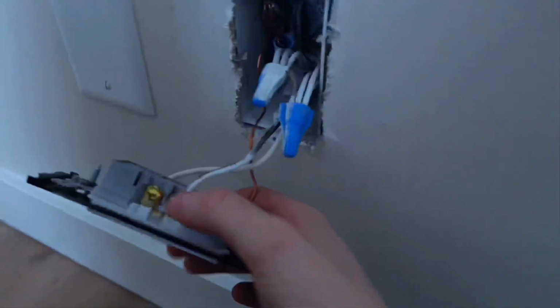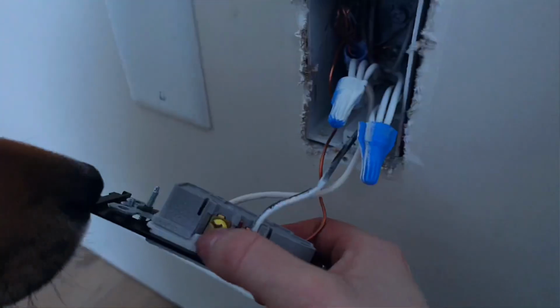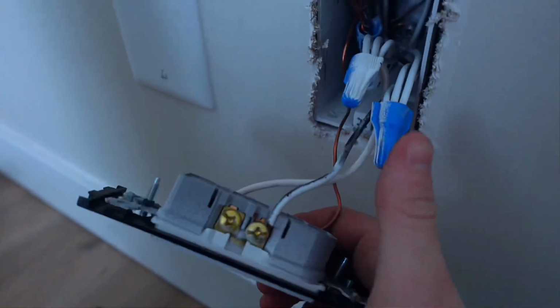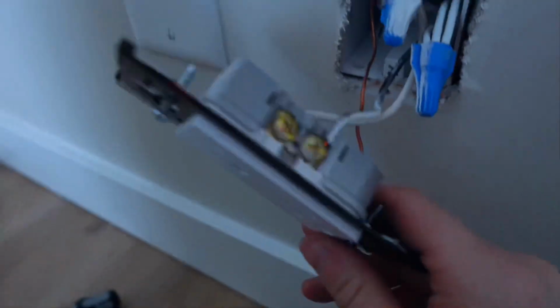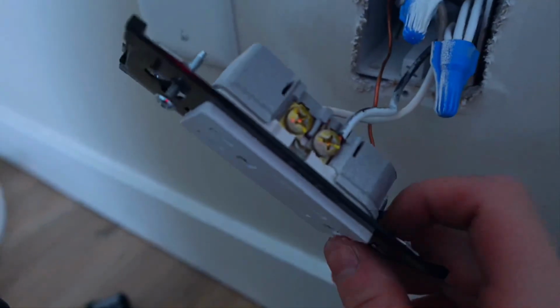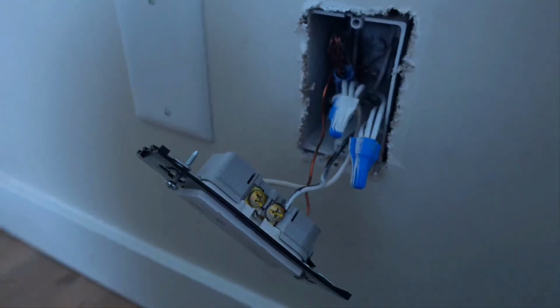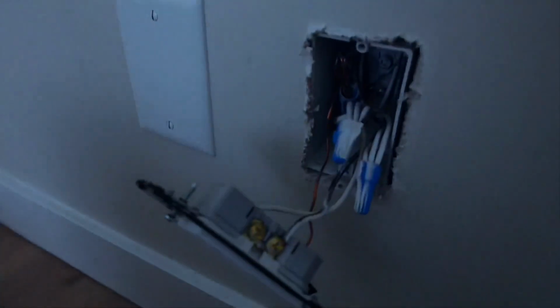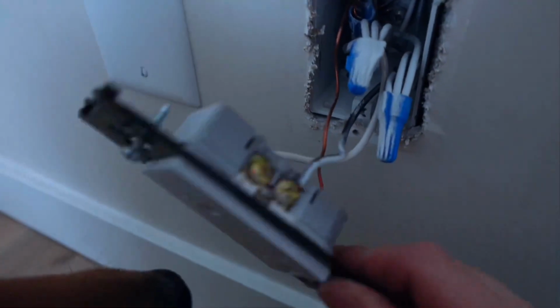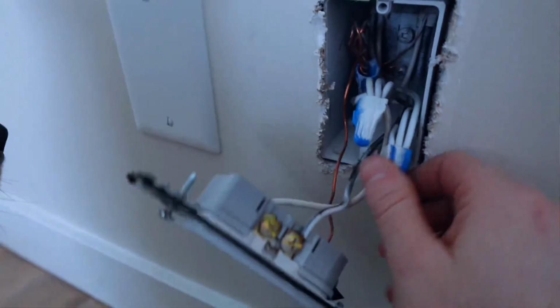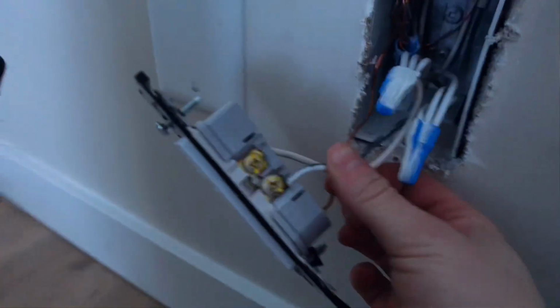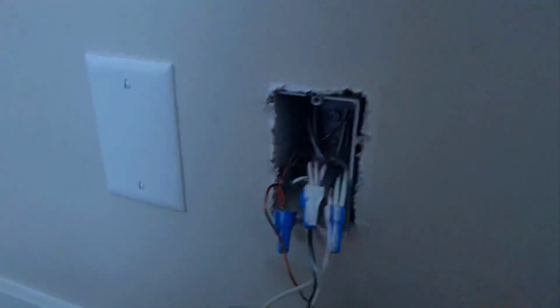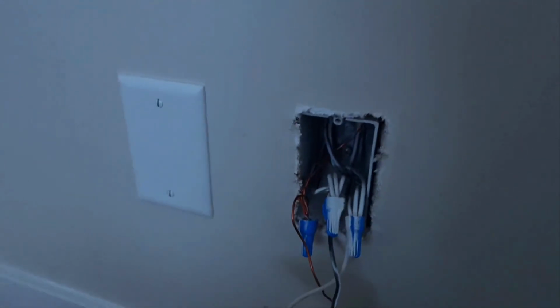So what happens is power is going to come into one screw, go through the device, and then come out the other screw. Right, Yeti? Which can cause a lot of faults because if the device fails, all of a sudden half your receptacles are going to stop working. So when you are doing this, please keep in mind that if you see the receptacle done incorrectly, it's important to change it, splice those wires together, and have a single pigtail coming out to the receptacle instead.